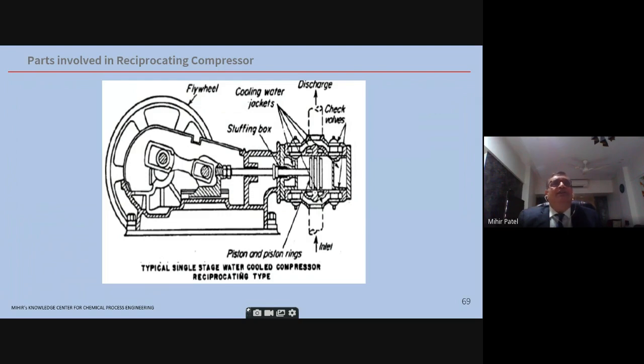The parts involved in the reciprocating compressor. So on the right, you see the main discharge head. You have the piston moving in it. Flow is from the bottom, discharge on the top. And you have a piston. So at the left-hand side, you have a flywheel, which is rotating and pushing the piston in and out. So this is a single-stage typical recip compressor.